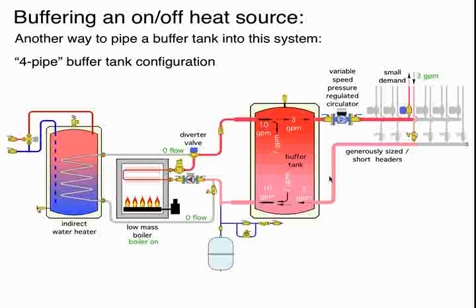The difference between the 2-pipe and the 4-pipe is the same scenario. It's really just the internal flow velocities in the tank that would be affected. So I would say either of these schematics would definitely be workable. Okay. And last question while we're on that slide, in sizing that buffer tank, in addition to the space heating load, are you also going to take into consideration your domestic volume in sizing?